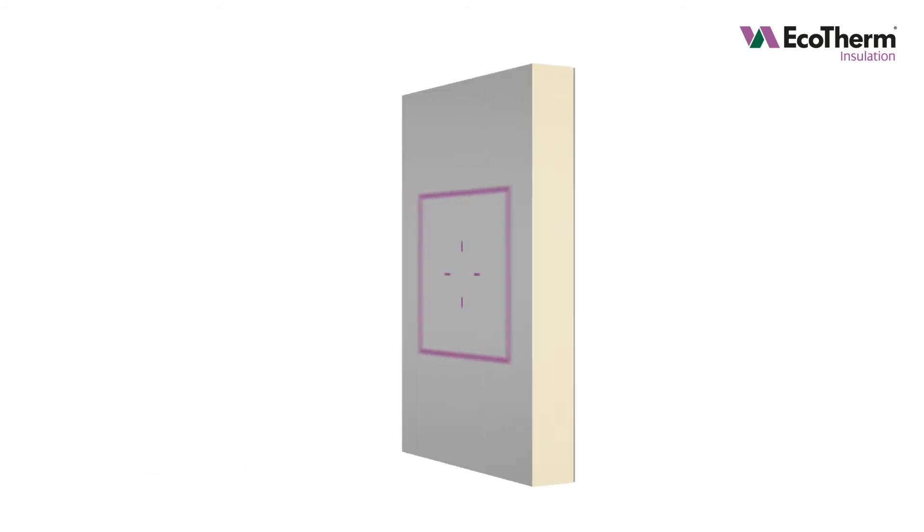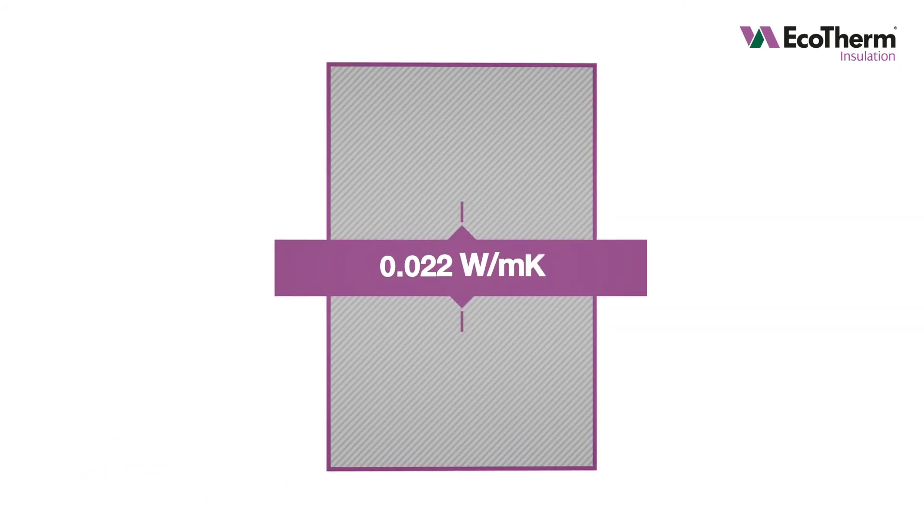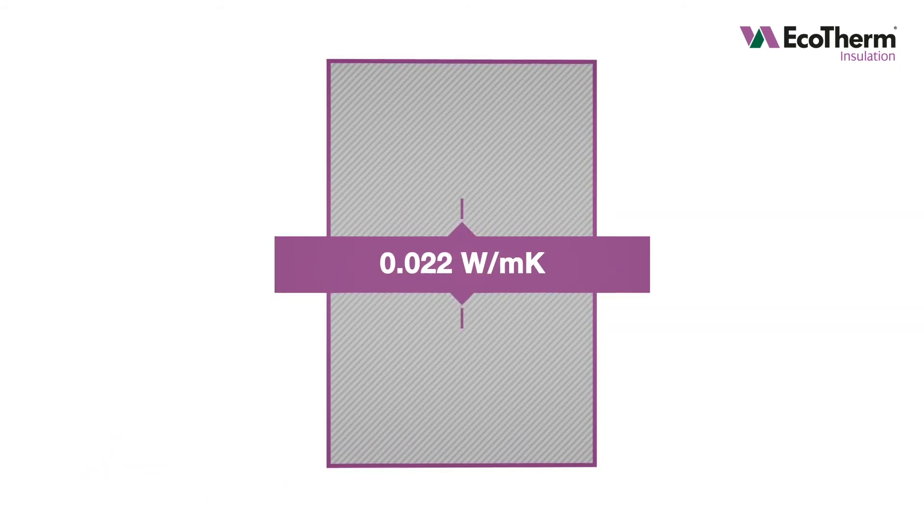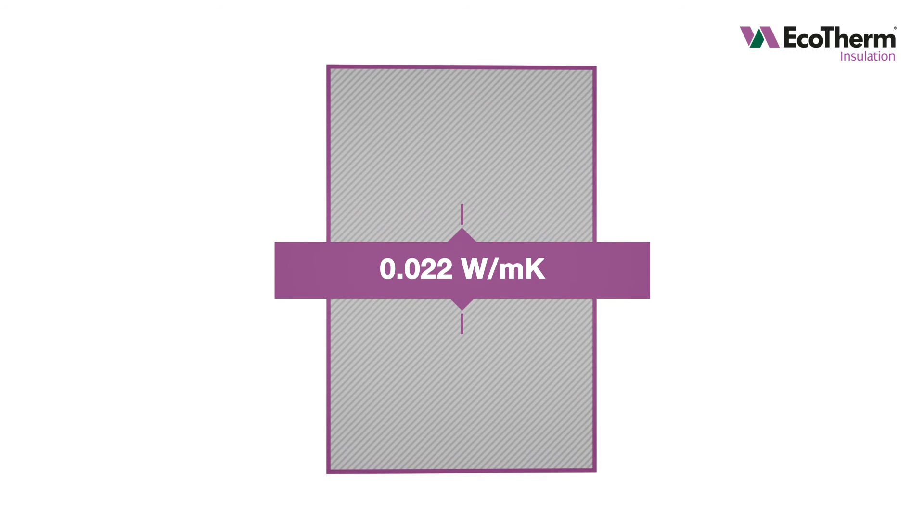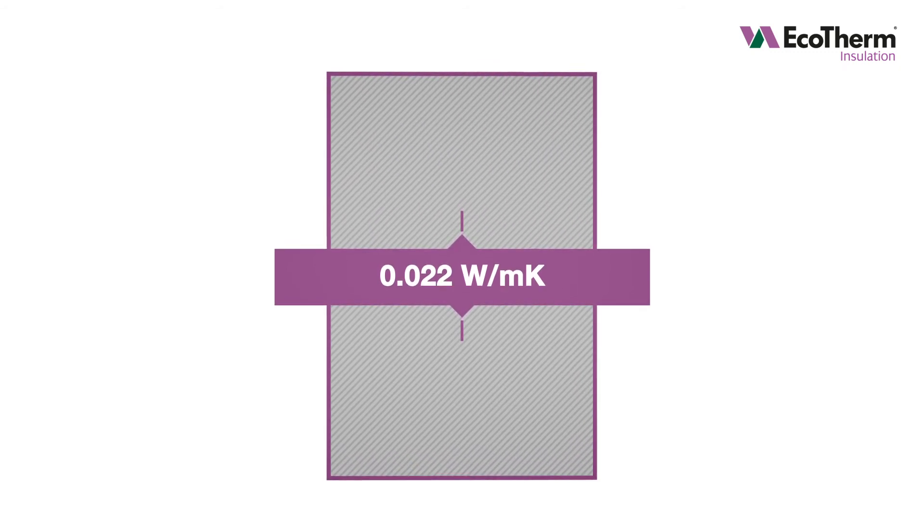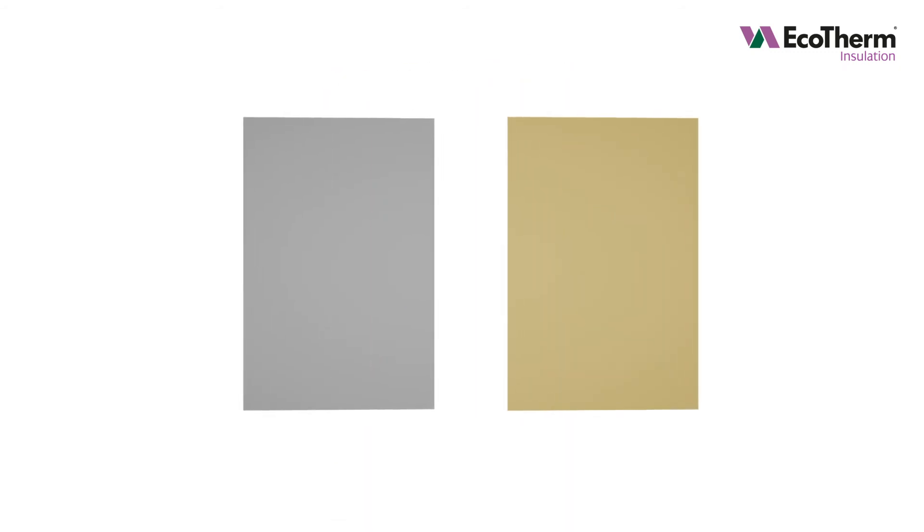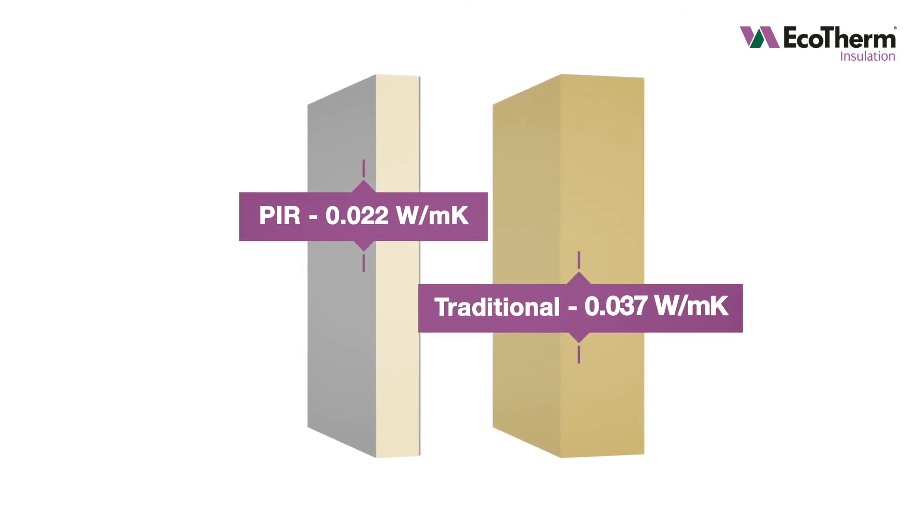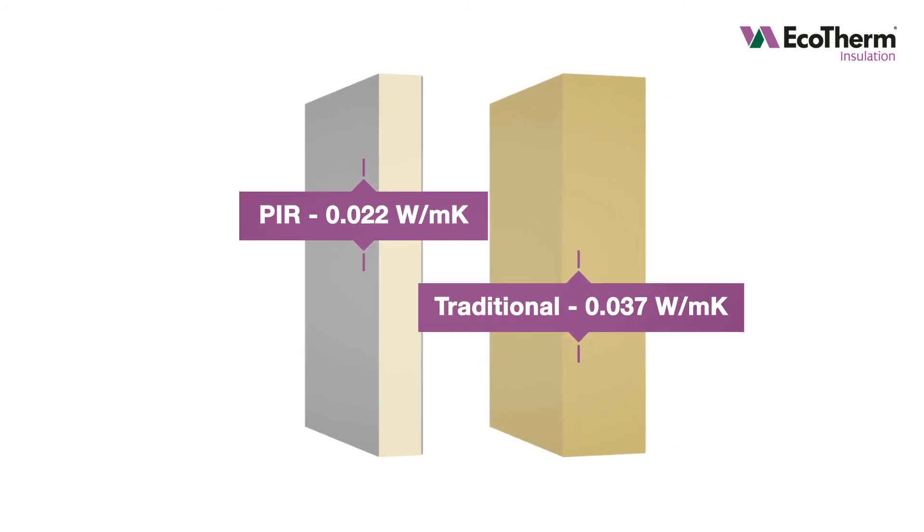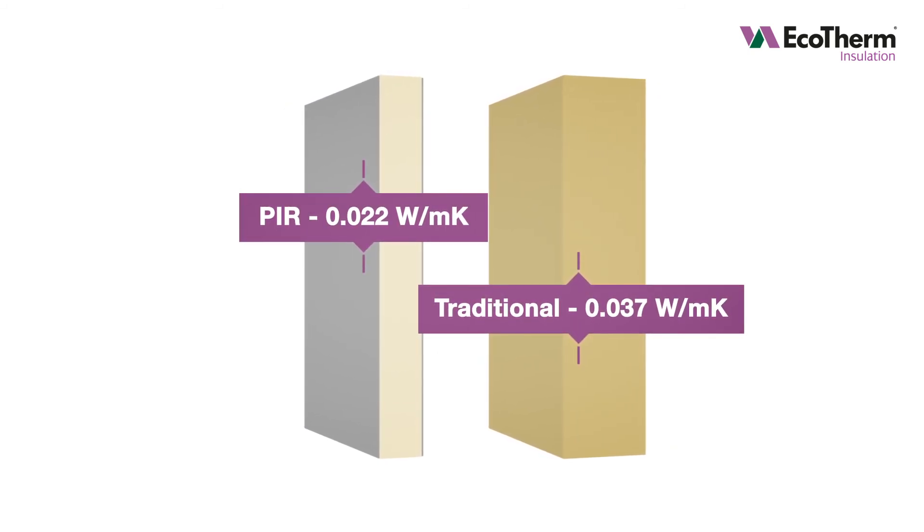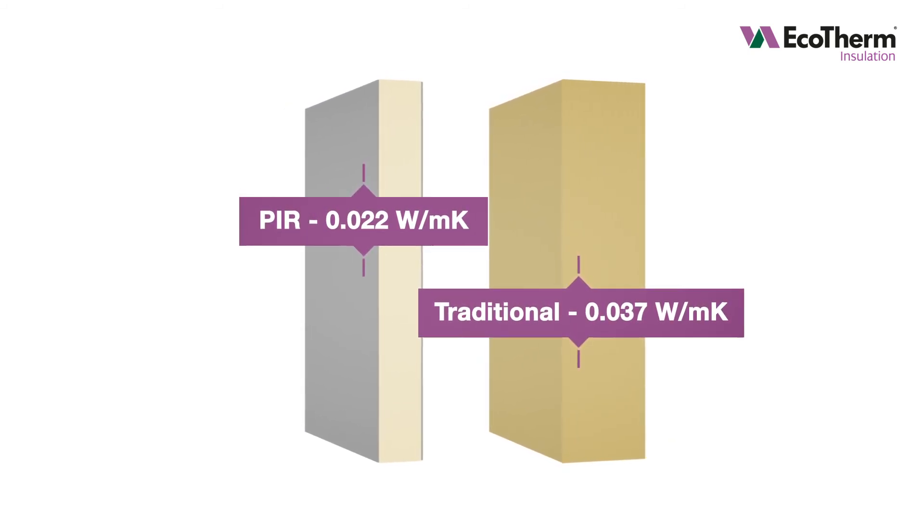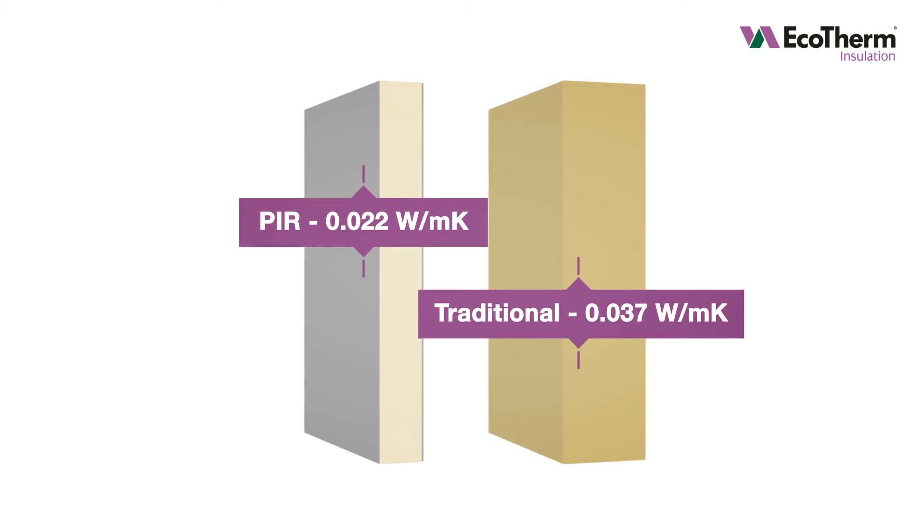Ecotherm insulation boards achieve low lambda values as low as 0.022 watts per meter Kelvin. This means PIR users require approximately half the thickness of traditional forms of insulation to meet the same level of thermal performance.